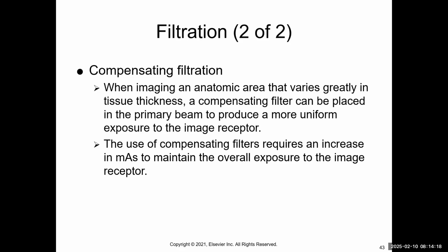So there's a lot of difference. So we can use those step wedge types of filtration to just even that out. Usually it does require a little bit of an increase. In other words, you could use the mAs that you need to use for the hip, and it's going to be fine for the ankle because of the added filtration in the compensating filter.